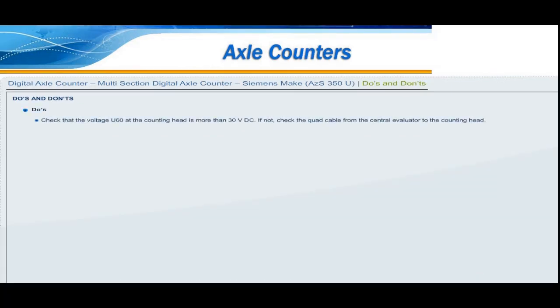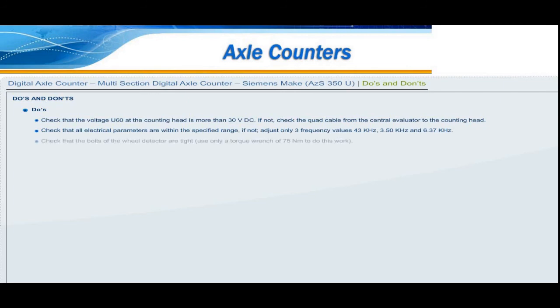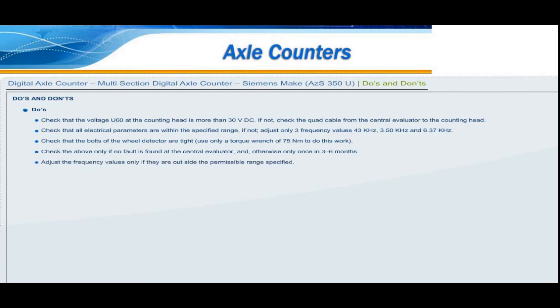Check that the voltage U60 at the counting head is more than 30 volt DC. If not, check the quad cable from the central evaluator to the counting head. Check that all the electrical parameters are within the specified range. If not, adjust only three frequency values: 43 kHz, 3.50 kHz and 6.37 kHz. Check that the bolts of the wheel detector are tight. Use only a torque wrench of 75 Newton meters to do this work. Check the above only if no fault is found at the central evaluator, and otherwise only once in 3 to 6 months. Adjust the frequency values only if they are outside the permissible range specified.